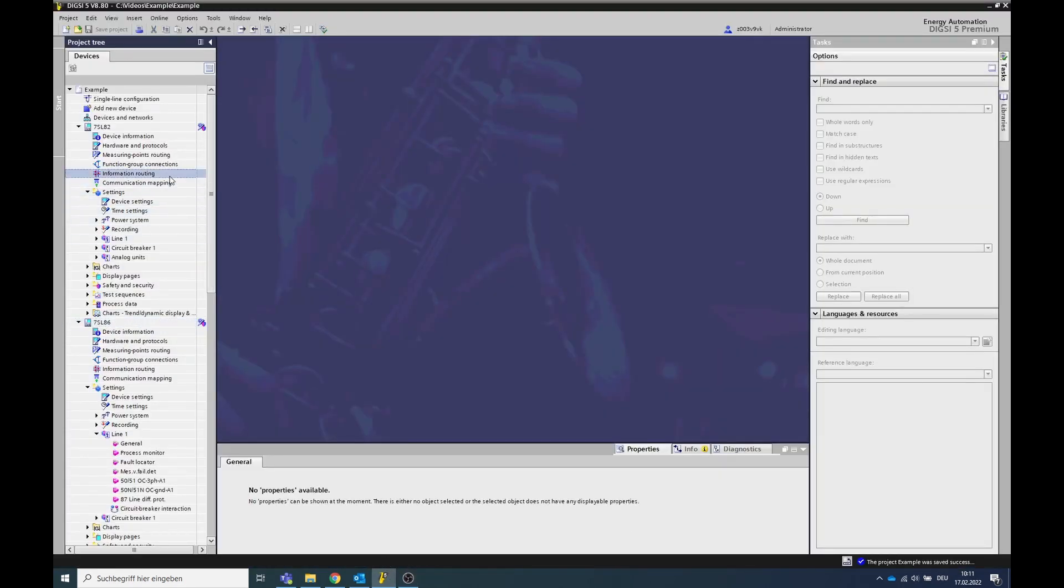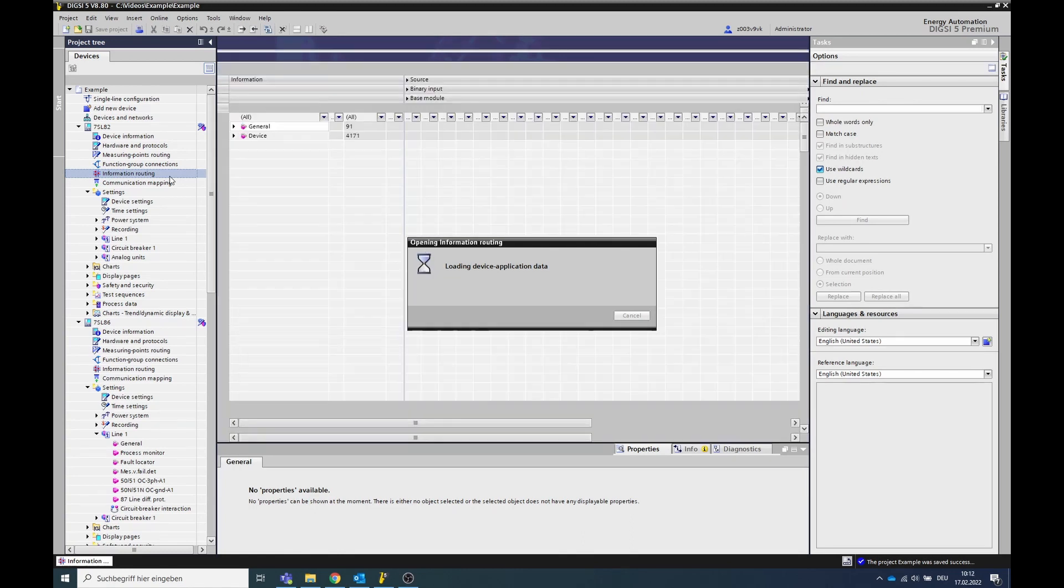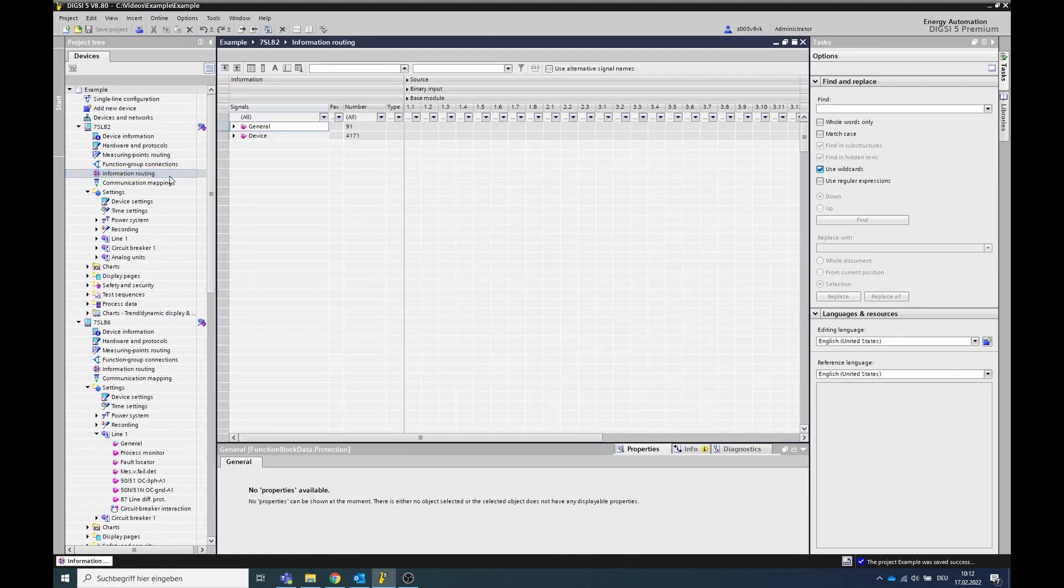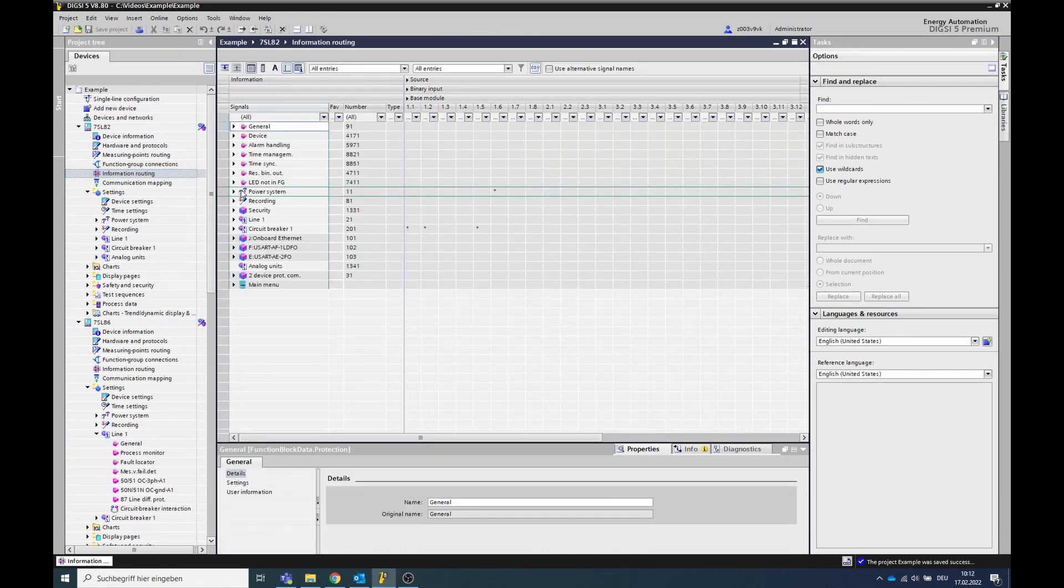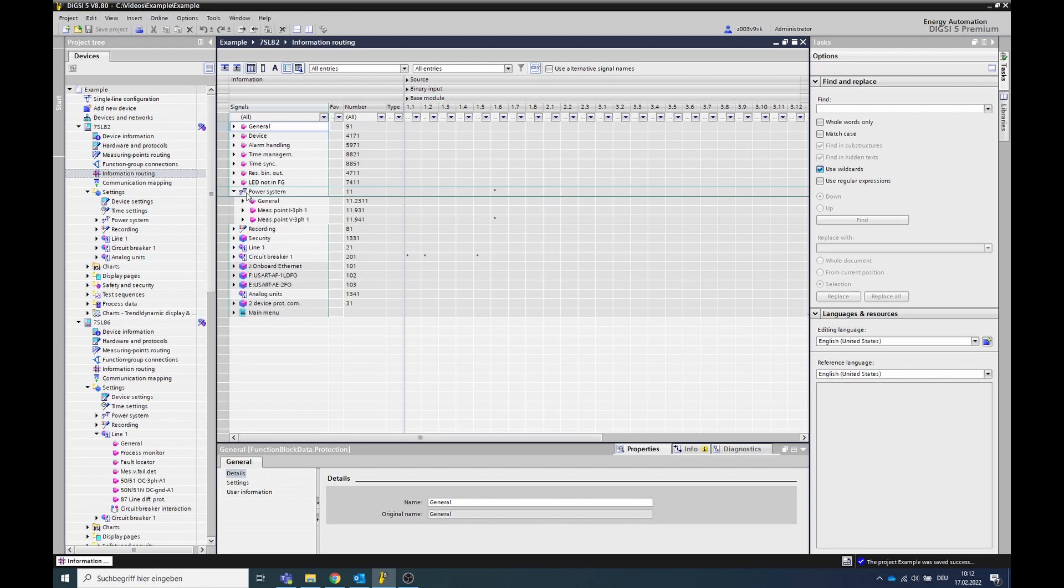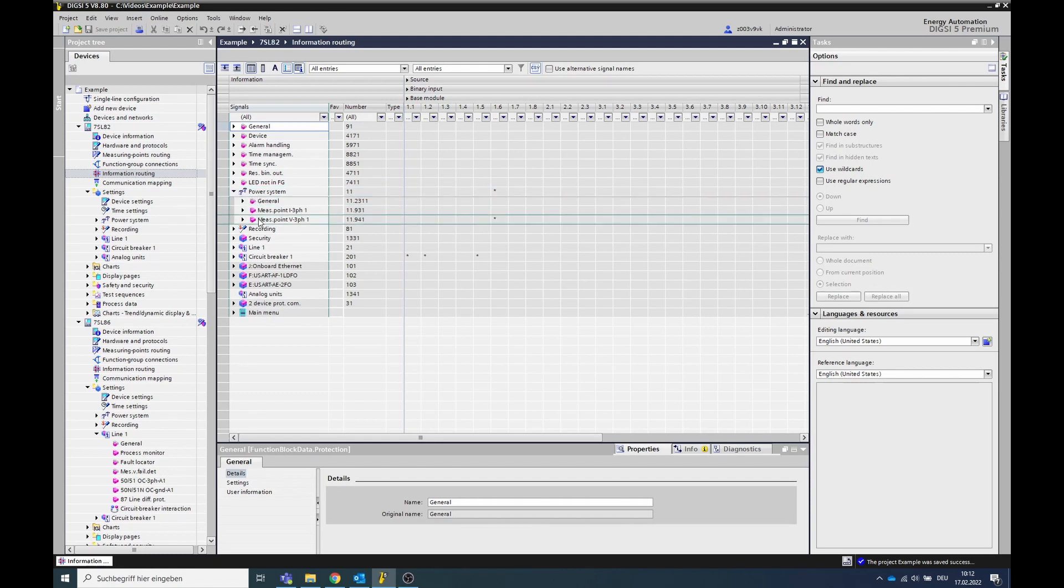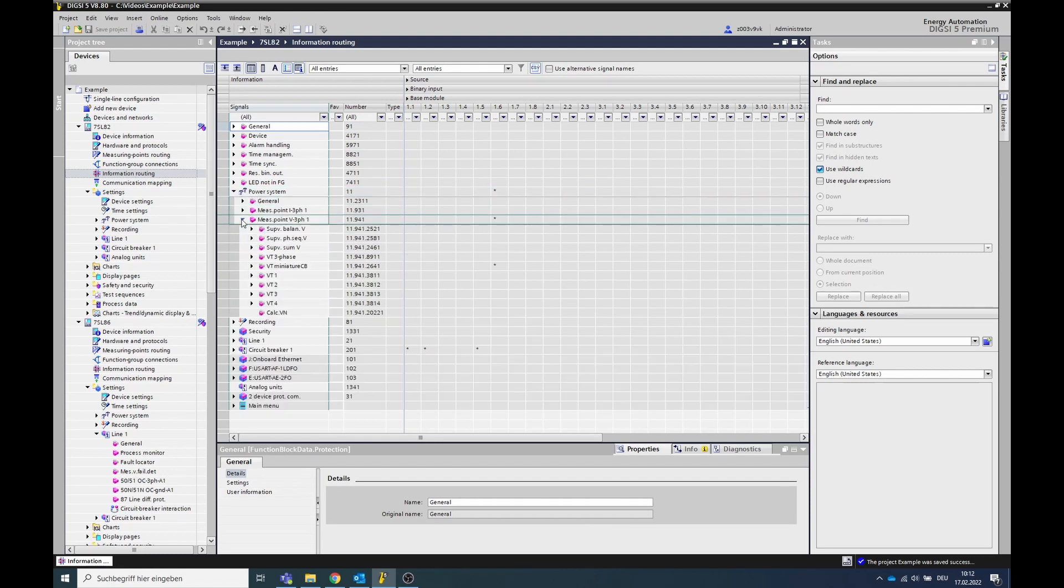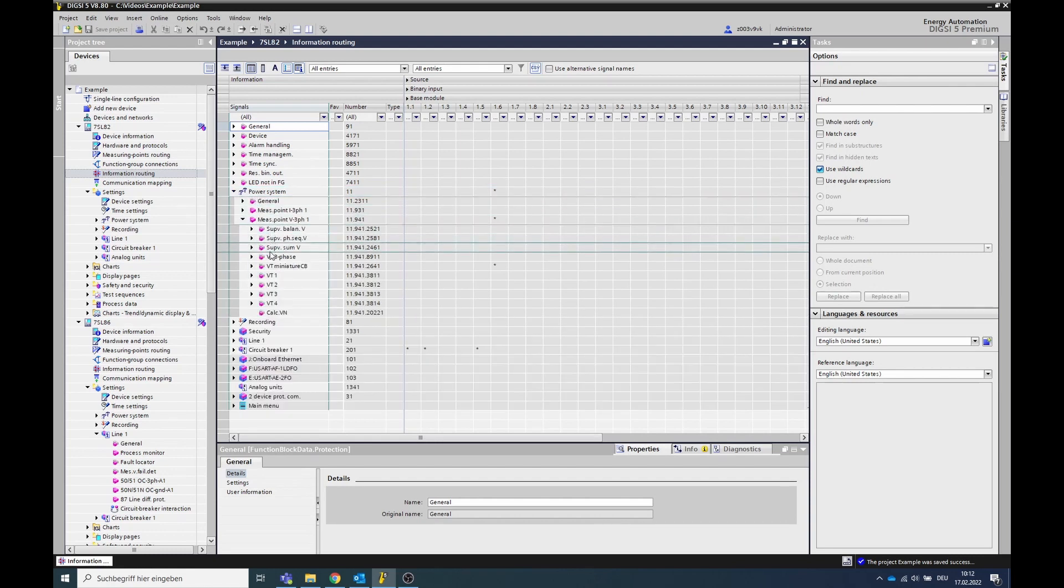To check this, first look which binary input detects the position of the voltage transformer circuit breaker. To do this, open the configuration file of the affected device in DIGSI and go to the information routing.